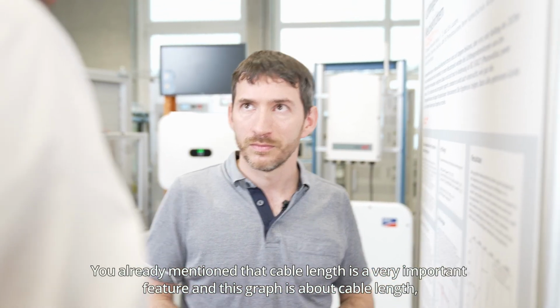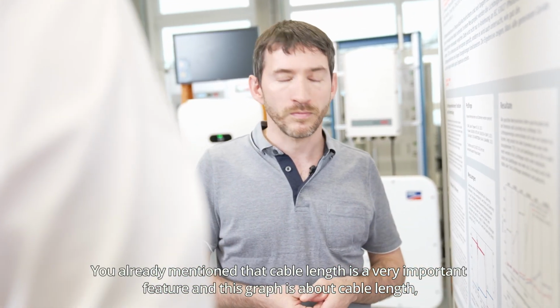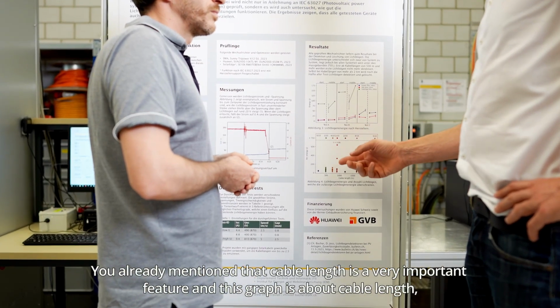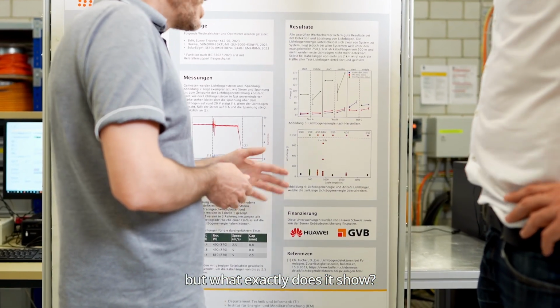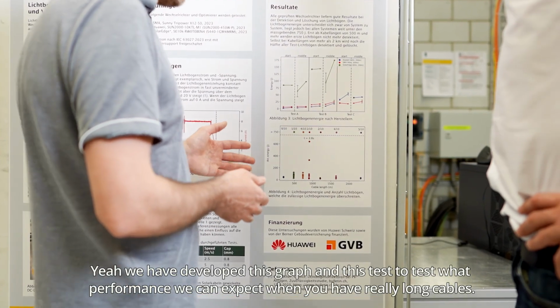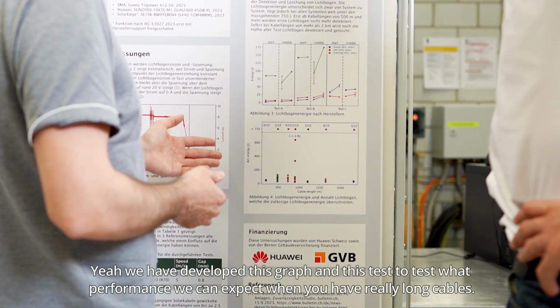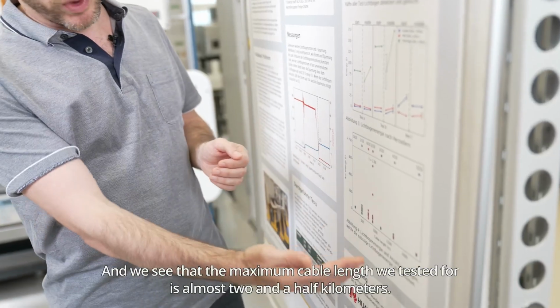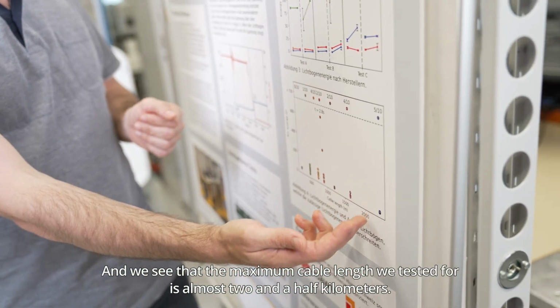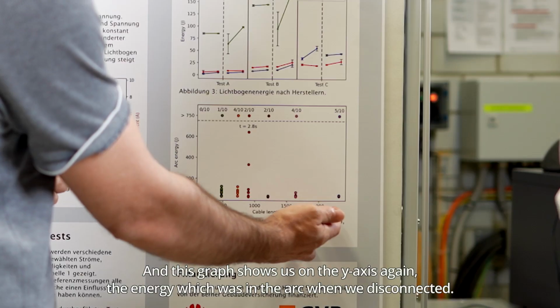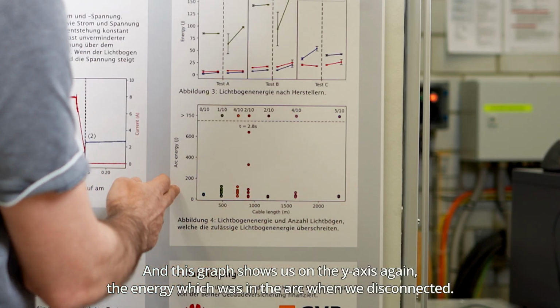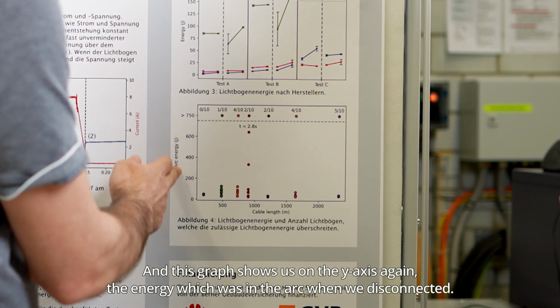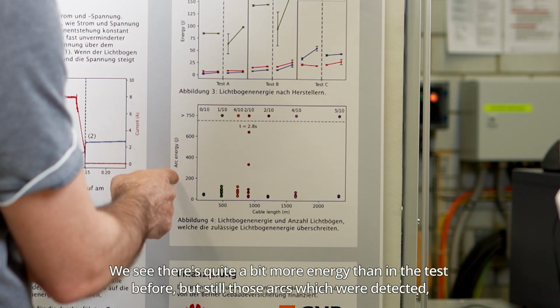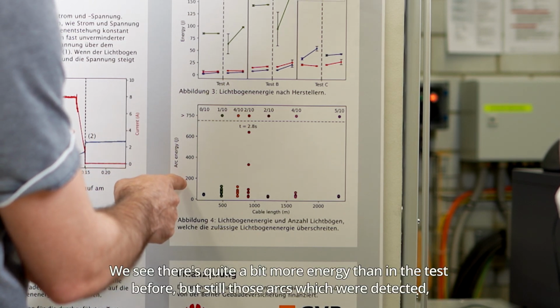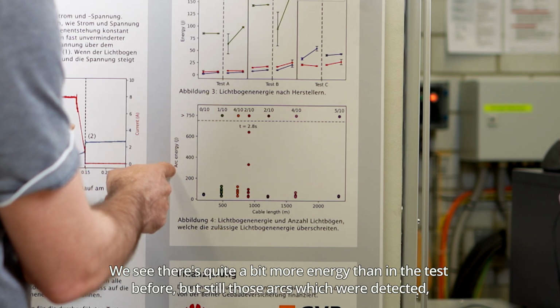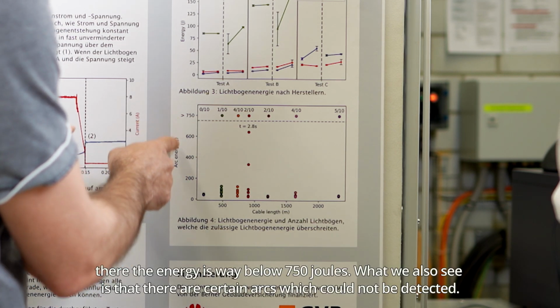You already mentioned that cable length is a very important feature. And this graph is about cable length, but what exactly does it show? Yeah, we have developed this graph and this test to test what performance we can expect when you have really long cables. And we see that the maximum cable length we tested for is almost 2.5 kilometers. And this graph shows us on the y-axis again the energy which was in the arc when we disconnected. We see there's quite a bit more energy than in the test before, but still those arcs which were detected, there the energy is way below 750 joules.